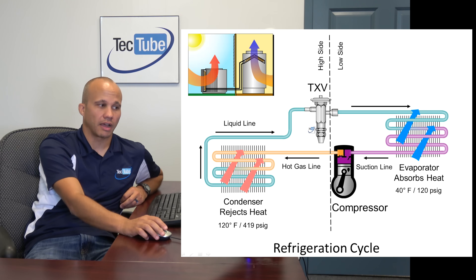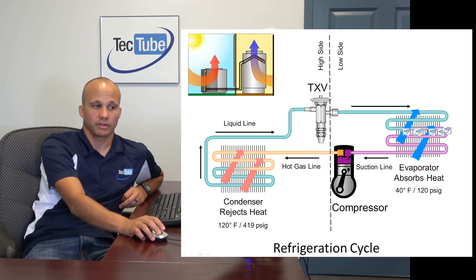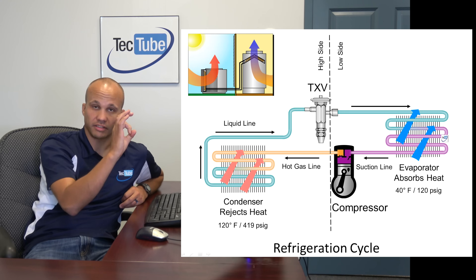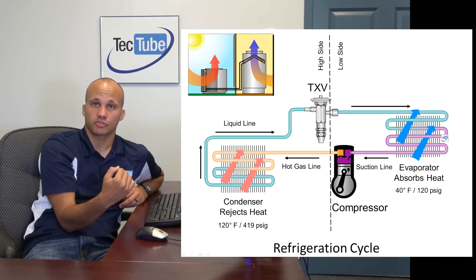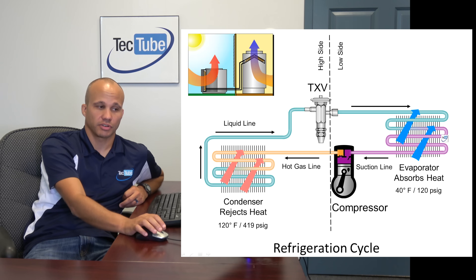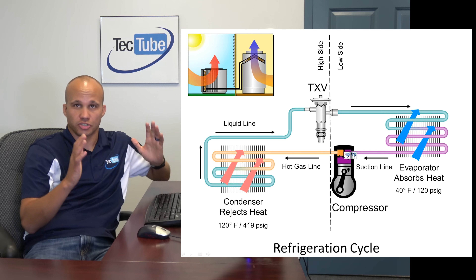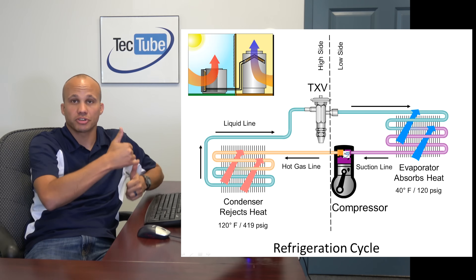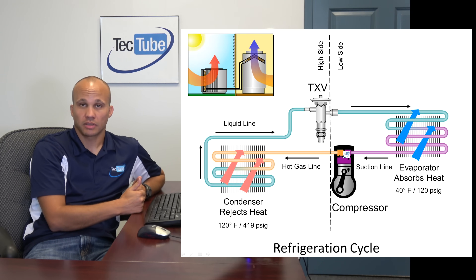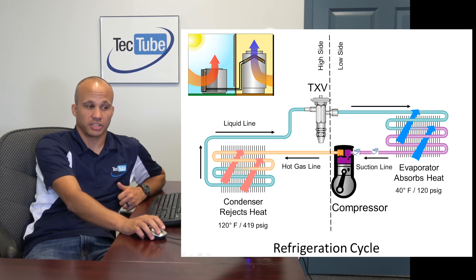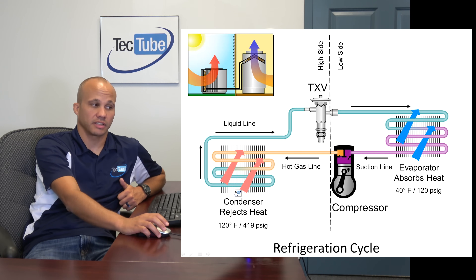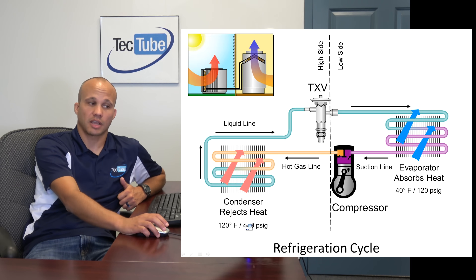Let's follow a refrigerant molecule around the loop, starting with the evaporator. The refrigerant molecule sitting in the evaporator is absorbing heat from the air of your house running through your furnace and evaporator coil assembly. As it absorbs that heat, the temperature of the refrigerant rises, and then it goes into the compressor, where the compressor raises the pressure even more. Because of the fixed volume, raising the pressure also raises the temperature. In our example, we start at 40 degrees in the evaporator coil and end up at 120 degrees in the condenser coil because the pressure was raised from 120 up to 420 PSI.